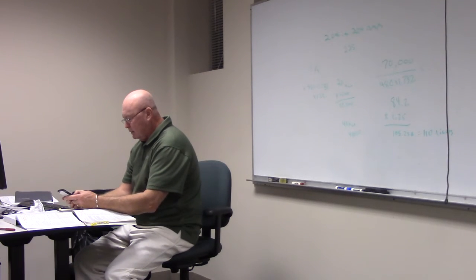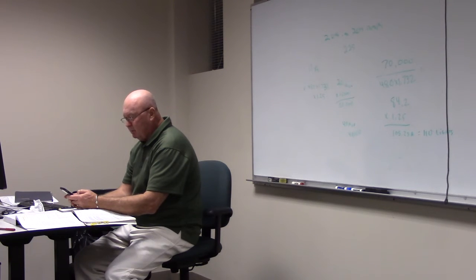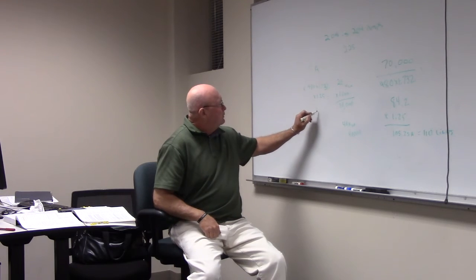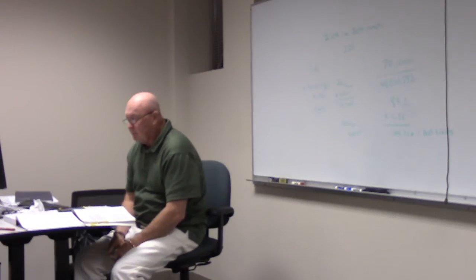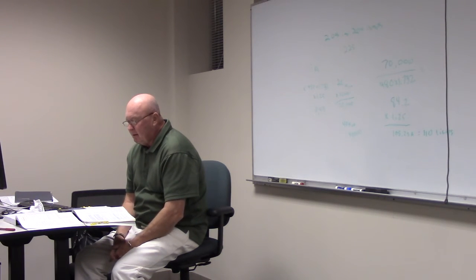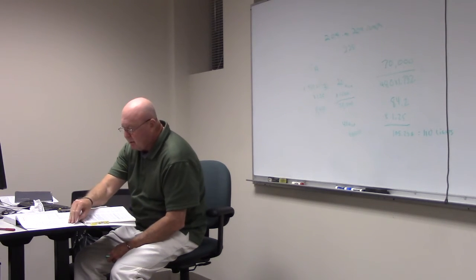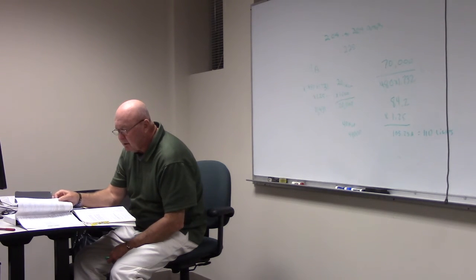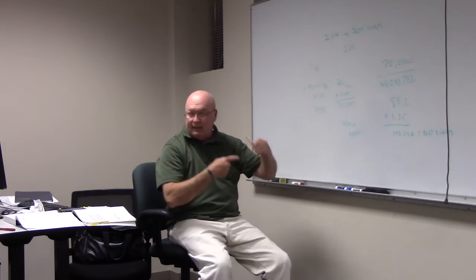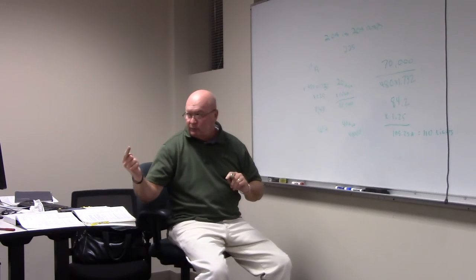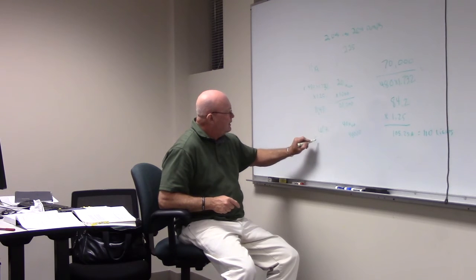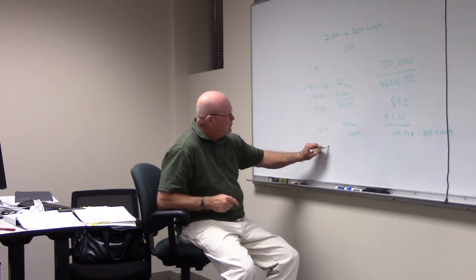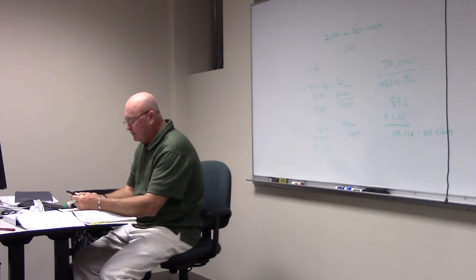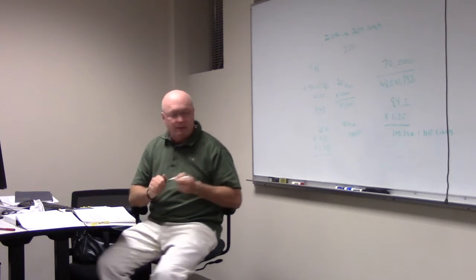11 times 480 times 1.732 times 1.25 should equal about 11,431. You agree with me? Yes. We have one thing left here: the 60 amp air conditioning unit. So 60 amps, and to get to volt amps we multiply by volts. It's 480 3-phase, so we're going to do 60 amps times 480 times 1.732. You with me? Let's see what we got there. 49,883. Yes.